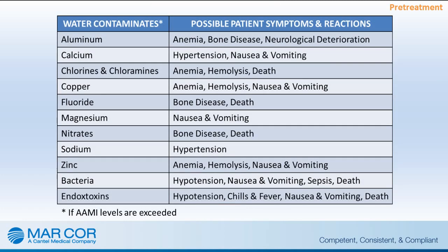Approximately 94% of the fluid in the final dialysate is composed of RO water, and if the water is not treated properly, the dialyzer membrane will be the only barrier between any contaminants and exposure of these contaminants to the patient's blood.